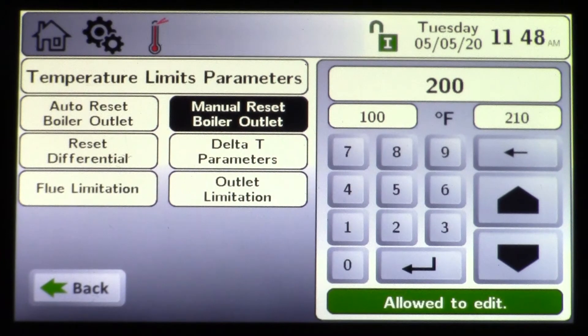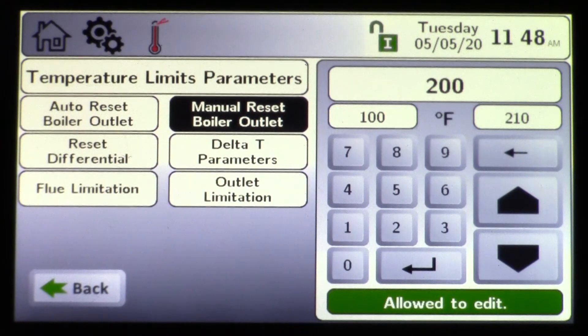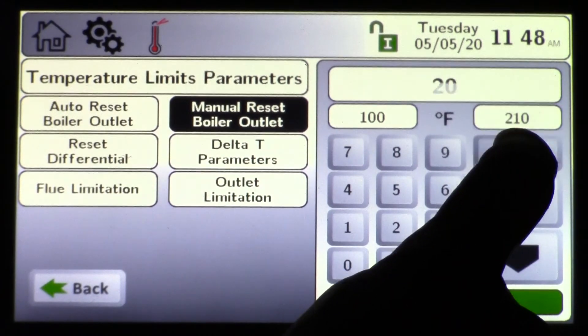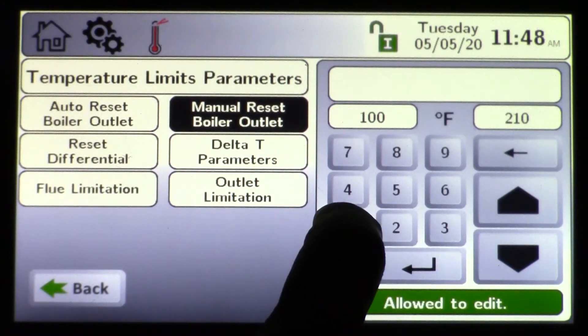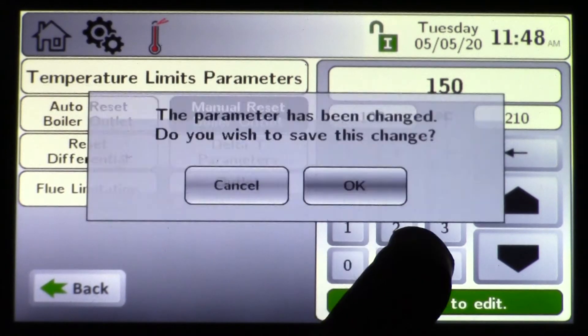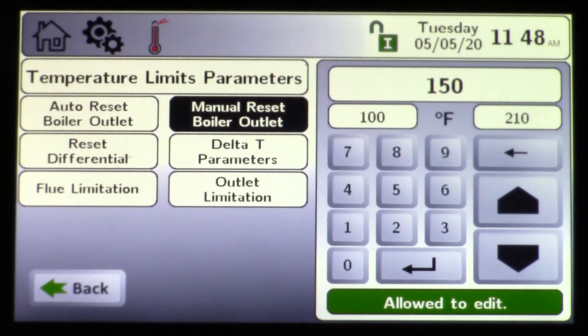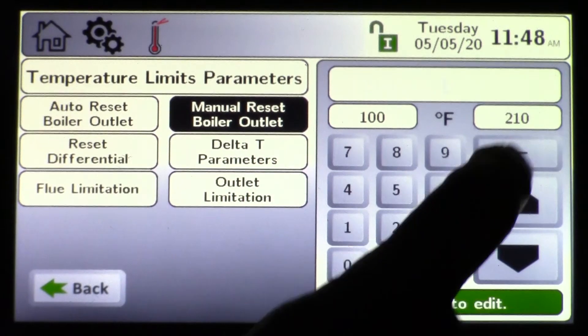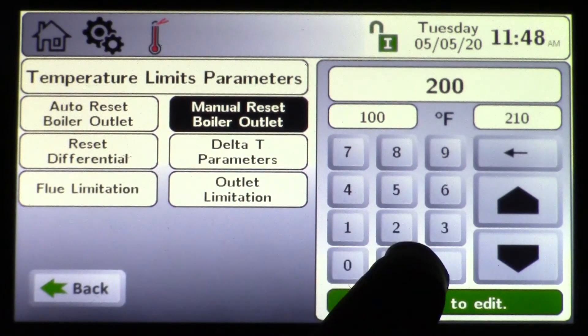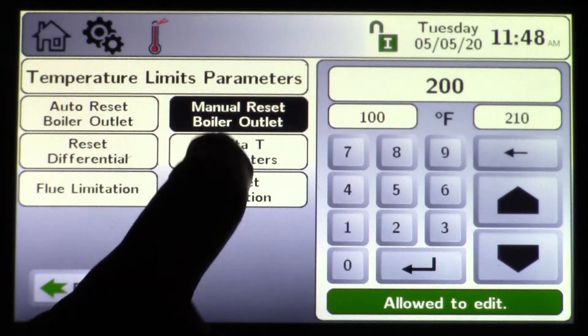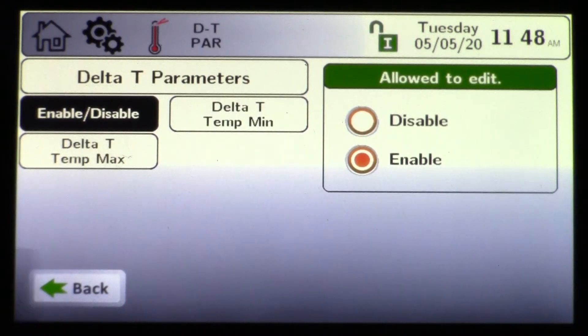Spread that out at least 10 degrees — that's an auto limit. A manual high limit means if I reach 200 degrees it's going to shut the boiler down and will not allow it to refire. If you need to test limits and an inspector is on the job, you can type in a lower value — hypothetically 150 degrees while the boiler is running at 160 — and once you click enter the boiler would lock out, proving to the inspector the limits work. Don't forget to go back and put that back up.